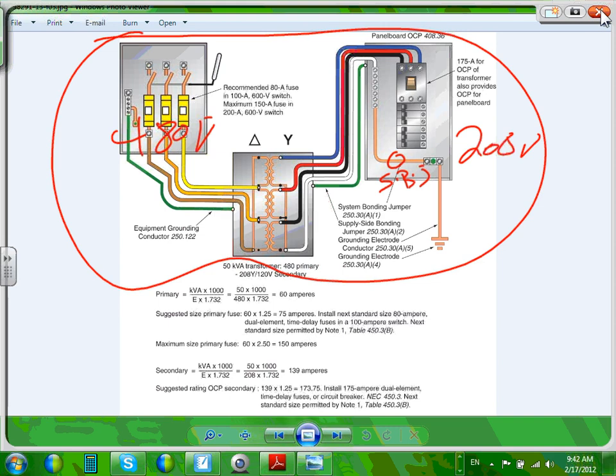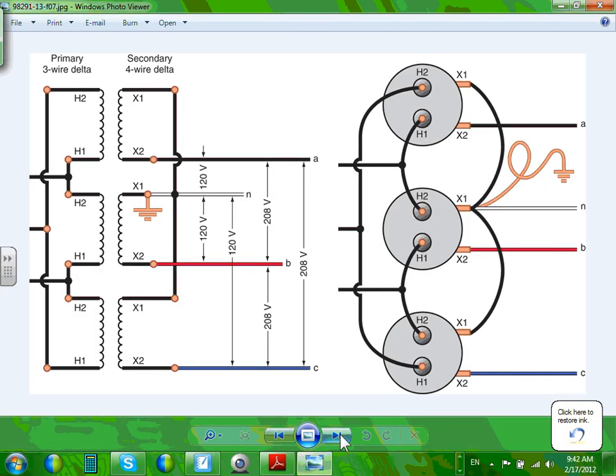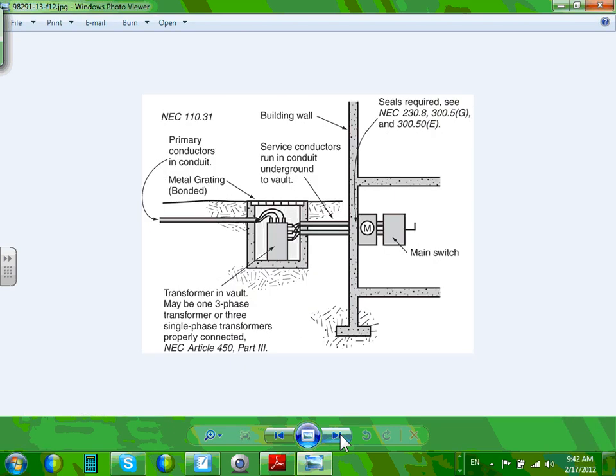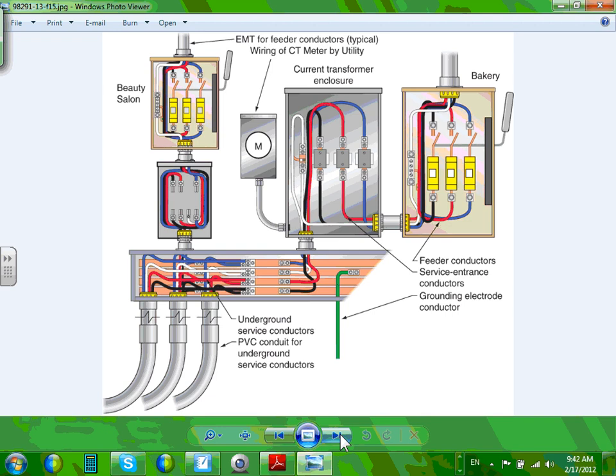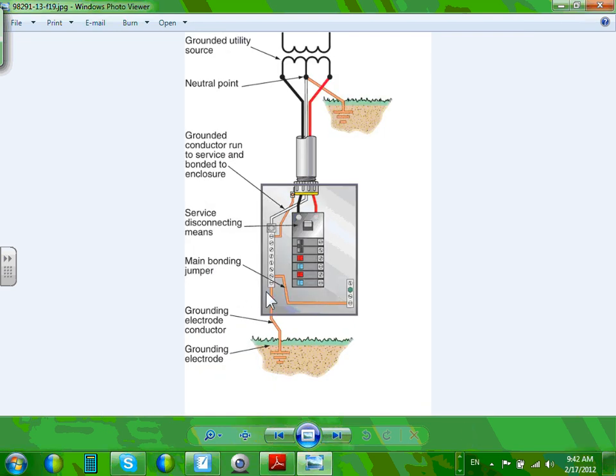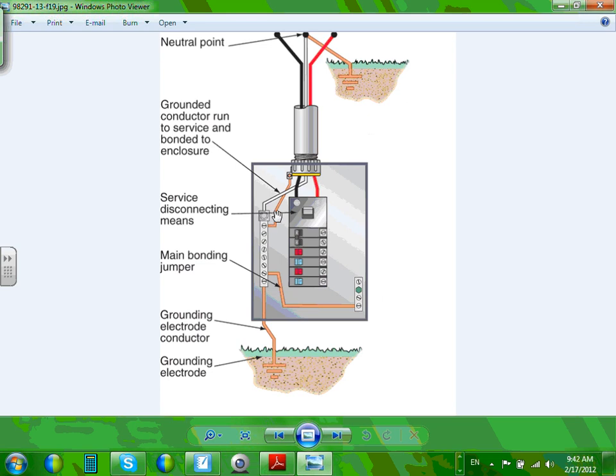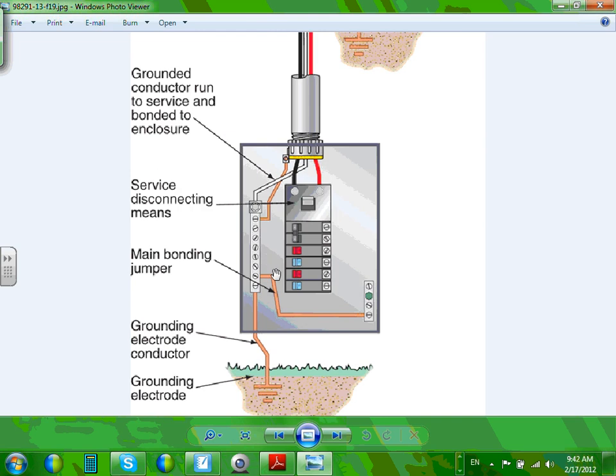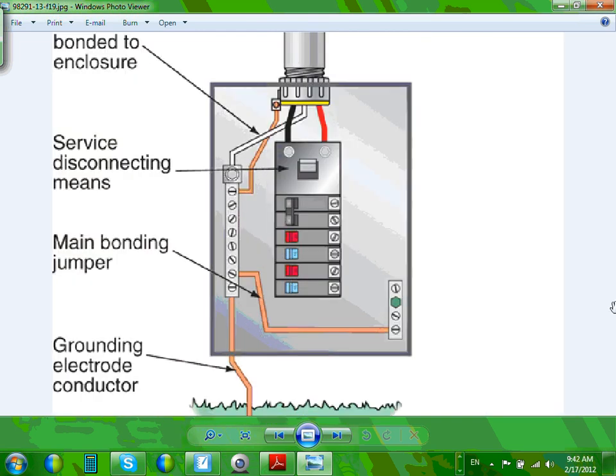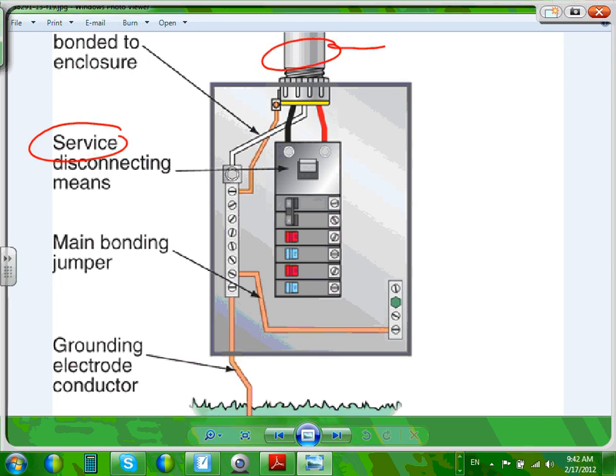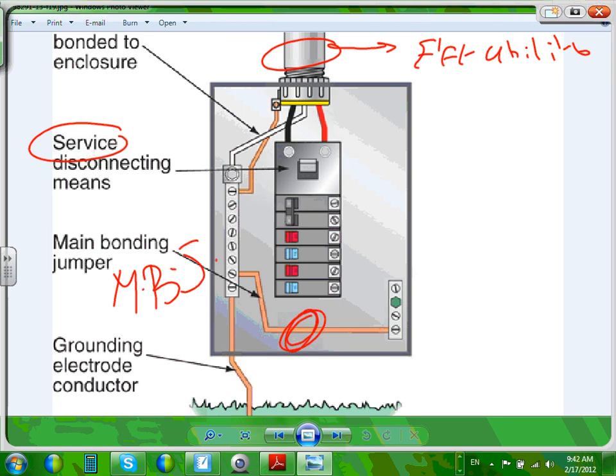Now, the second one is right at the service. I think we have a few of these at the service. Okay, here, this is not as clear. A lot of people see that. So this is the grounding conductor. This is the service disconnect, main bonding jumper, right in here. Can you guys see that? I want to remind you, this is the service disconnect. This power is coming from the electric utility, not from a feeder. That's my service panel. Right inside the service panel, that cable is called the main bonding jumper. They are the same. They do the same job. They are just called different names. We size them the same. Cool?